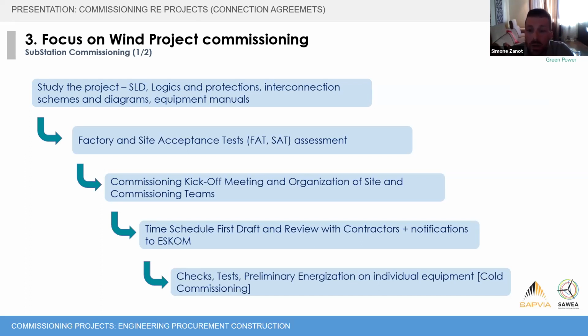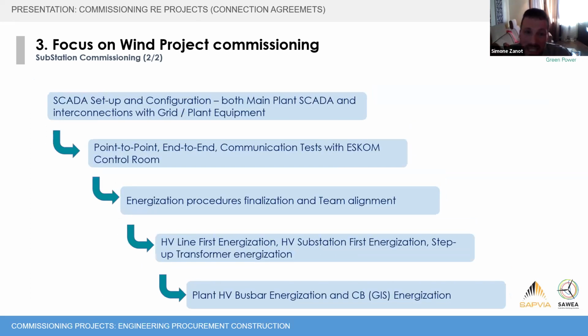And then we perform the cold commissioning. We finally set up the communication in order to perform the point-to-point and end-to-end communication testing with ESKOM. We finalize the procedure, and then we are authorized by the transmission system operator to energize our substation, and then our bus bar, the circuit breaker, and the gas insulated switchgears.